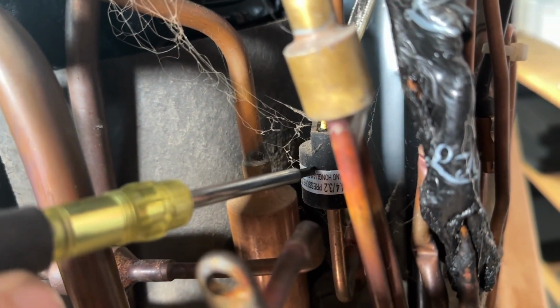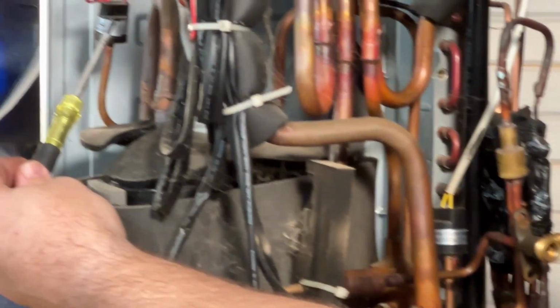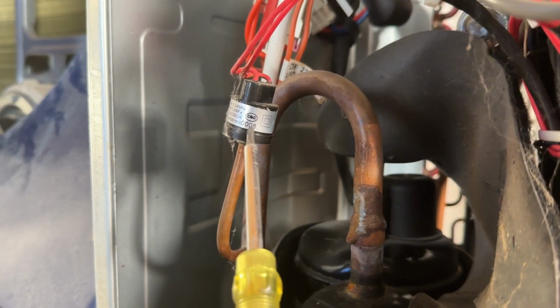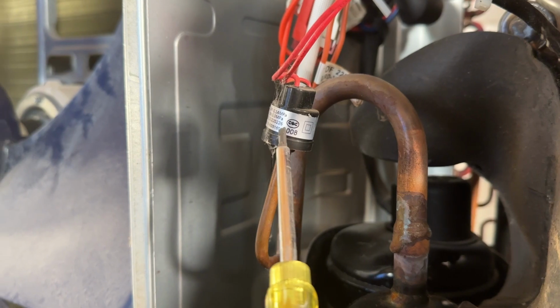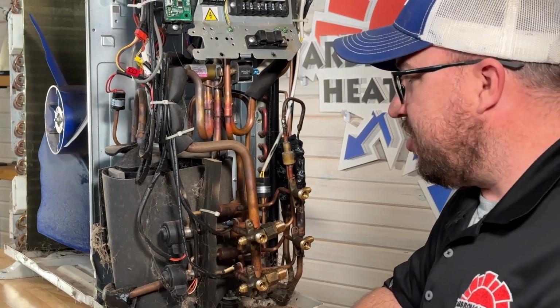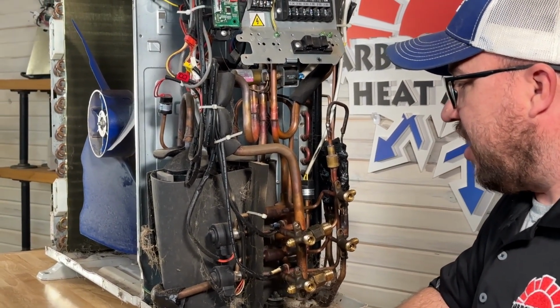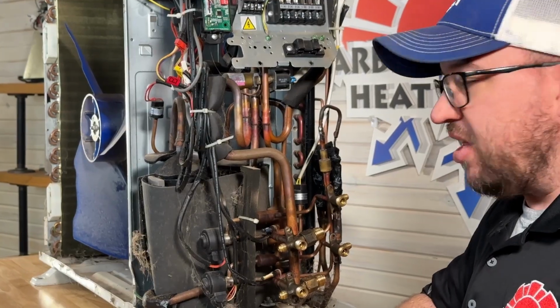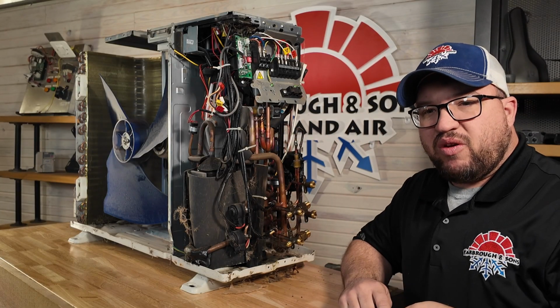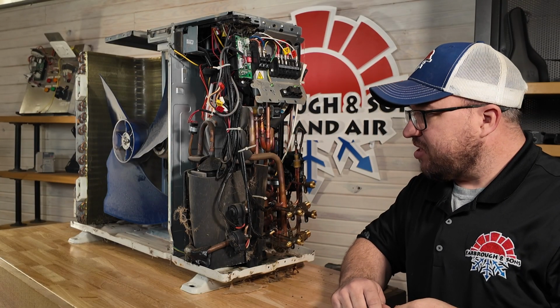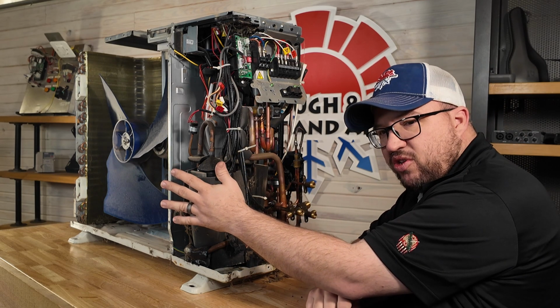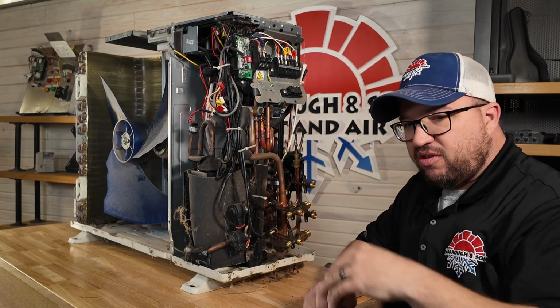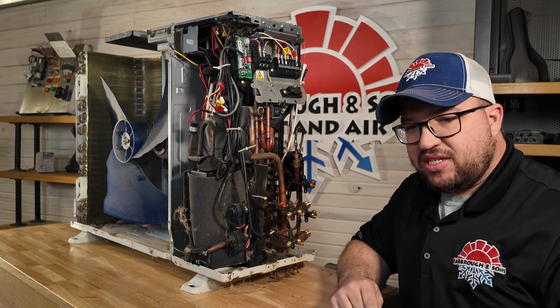So from there, we can go ahead and go with some of the safety devices. This one right here is a high pressure switch, and this one over here is a low suction pressure switch. Those are just to make sure that nothing happens to your unit, that you're not running it at too high a head pressure. Let's say you had a dirty coil and we are getting to pressures that could cause harm to this compressor or other components. We want to make sure we shut down that system.